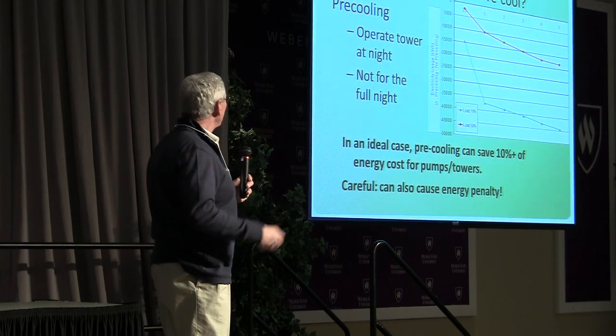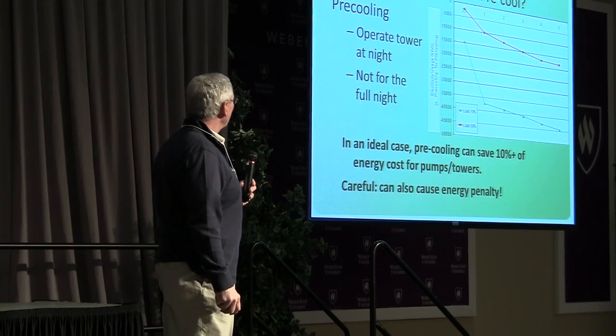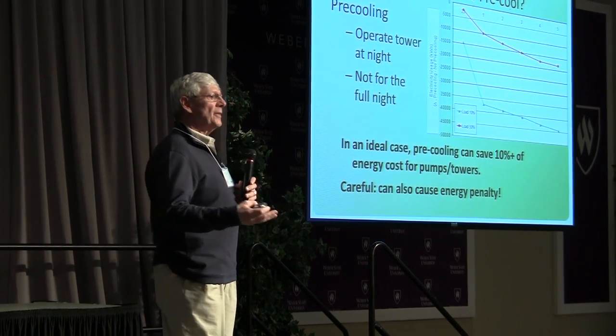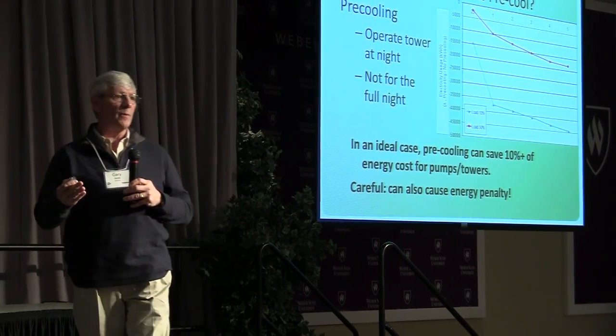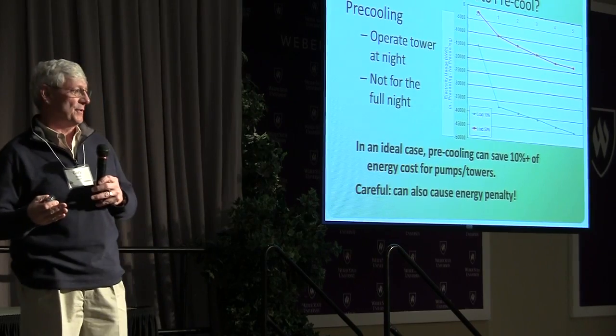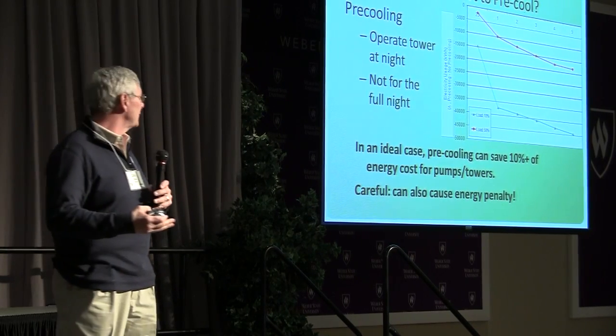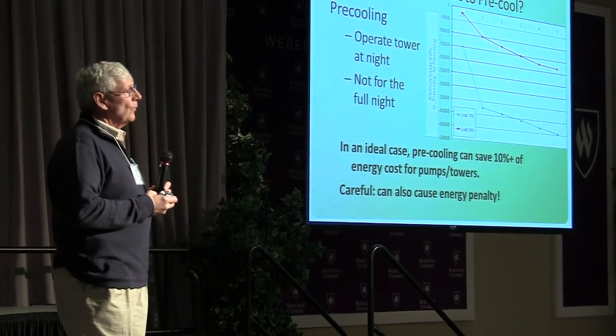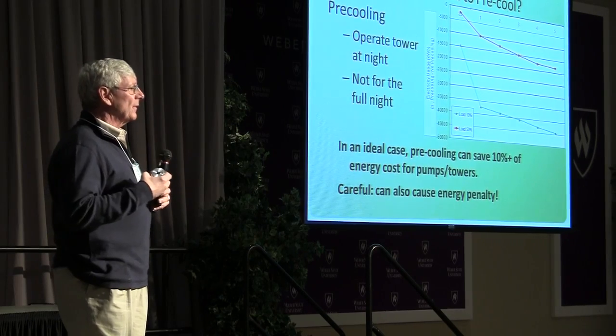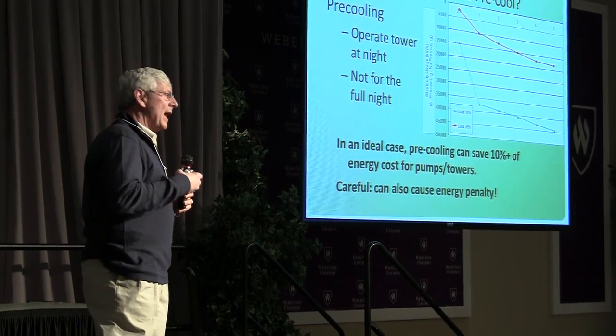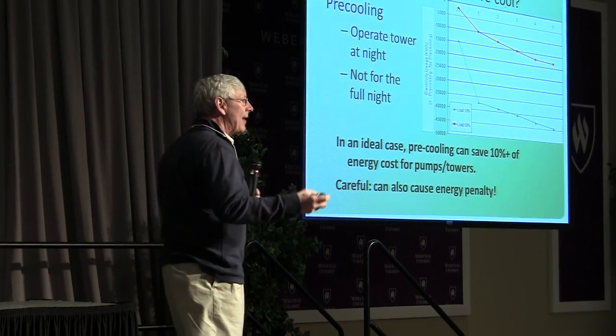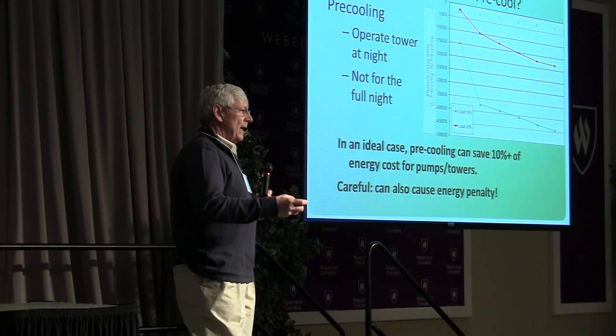Think of the ground loop as the thermal storage system. If we've got that, we found out we could do some load shifting. We could play with the cost of the system and the cost of operations. So we started moving energy into the ground in cooling-dominant situations, then taking it out at night to get rid of it.